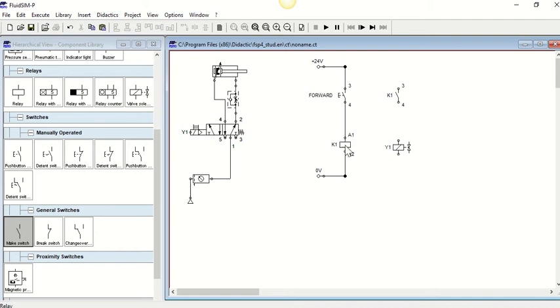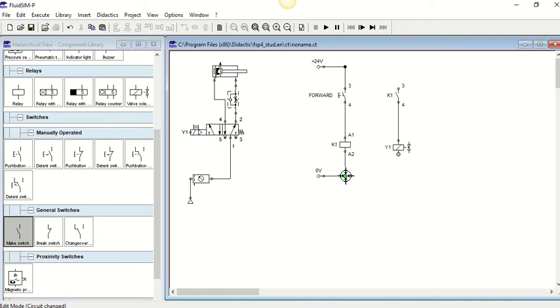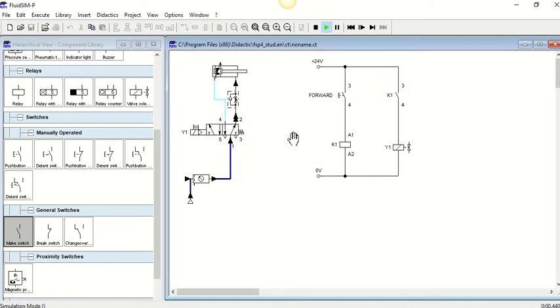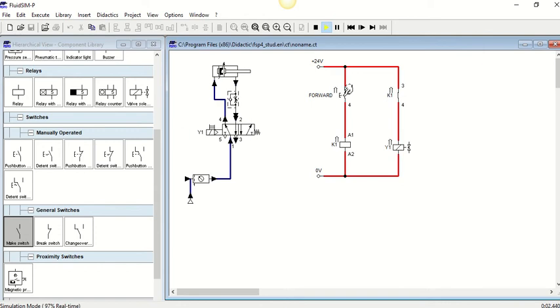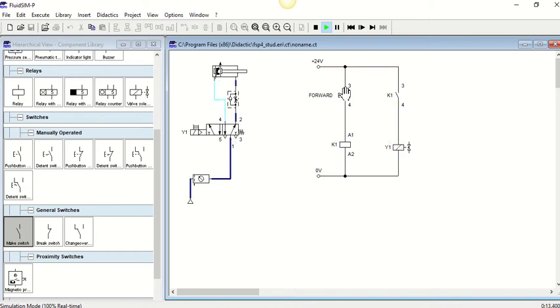This K1, what that means is once we give power to this K1 it is going to close over that switch. If we use the break switch it would open it up. Now nothing really has changed too much in the circuit. Some people would say it is probably over complicated for the moment. But you will see if I click the forward button K1 gets activated. If K1 gets activated anything that is called K1 closes over and then gives the supply to Y1 and it follows through.